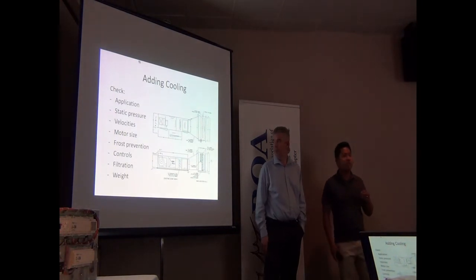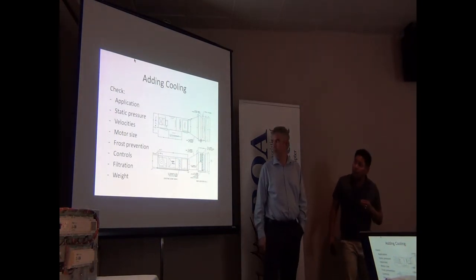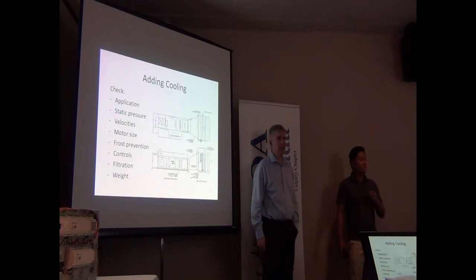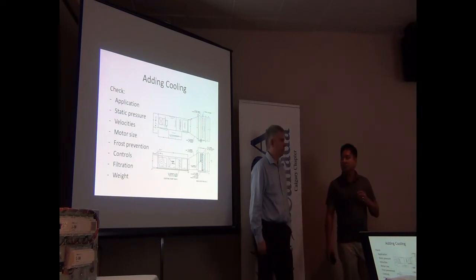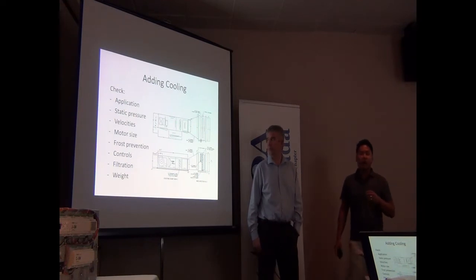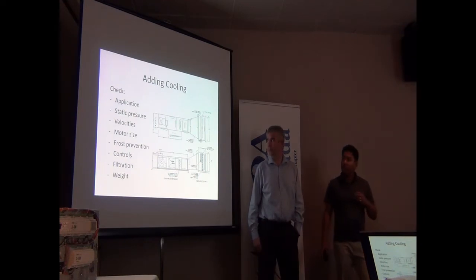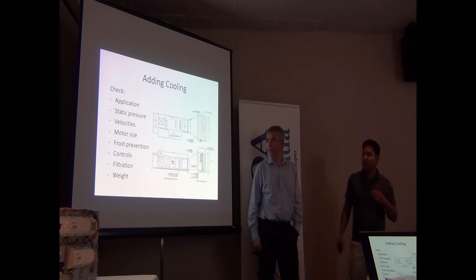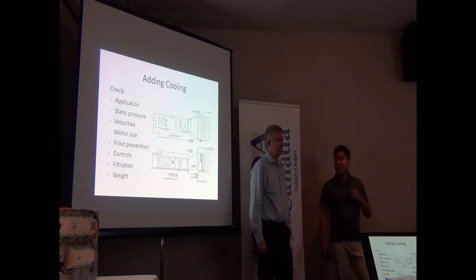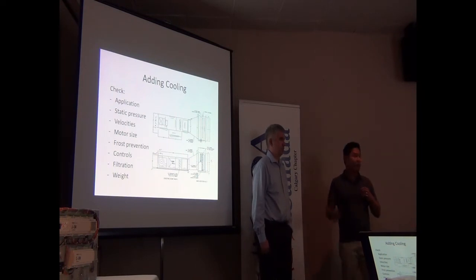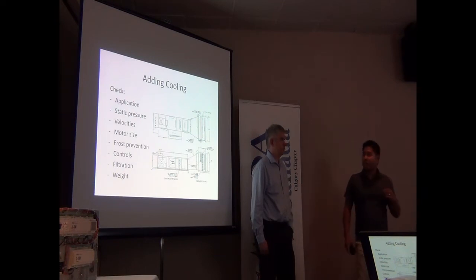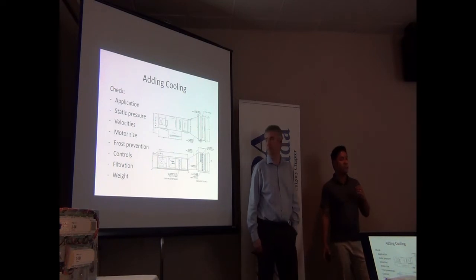This is a common question we get asked a lot: can we add cooling to your existing unit? It's not as straightforward as just adding a coil in the duct and saying you're good. You've got to look at your application, how much static that would add to the system, and your velocity. For example, a direct fired makeup air unit has high velocity airflow, so likely your coil will require a larger cross-section area. You also have to look at whether your existing motor can handle the additional static.